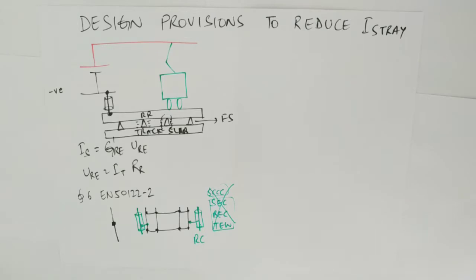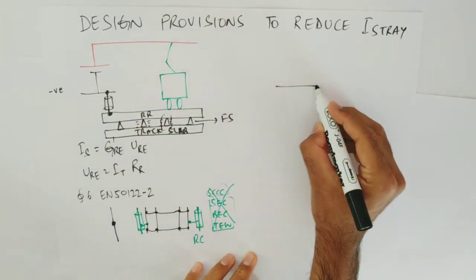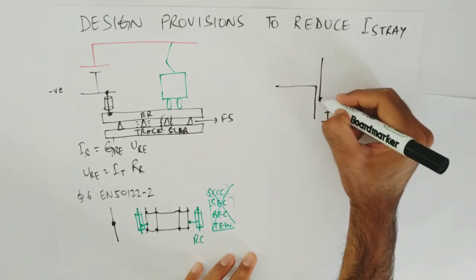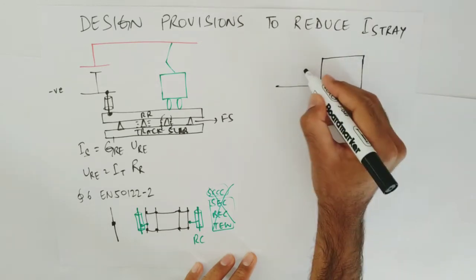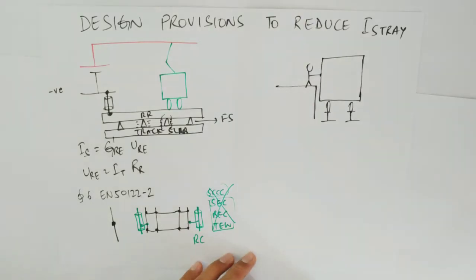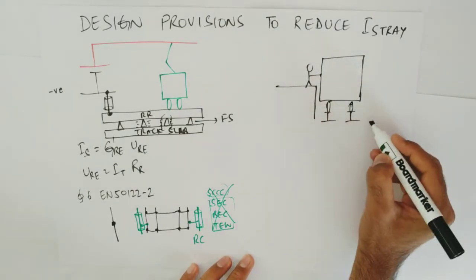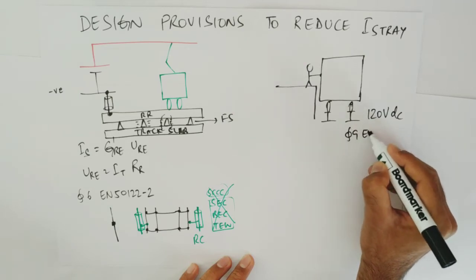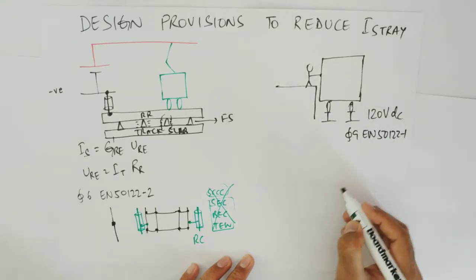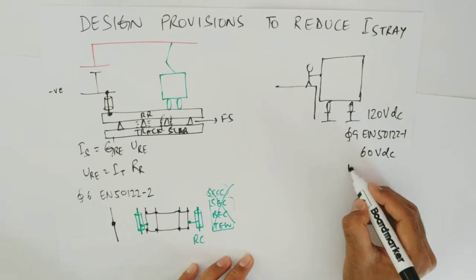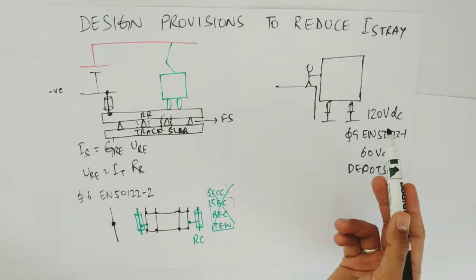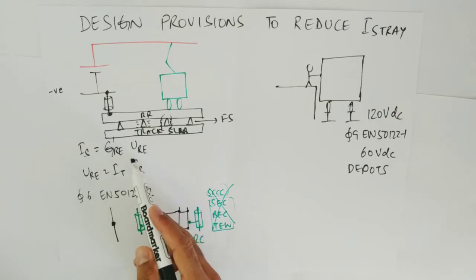However, this has a problem. Suppose we have a station with a platform and running rails, and a person is standing and touching the train. By touching the train he is exposed to the running rail potential. If the running rail potential is above the limit of 120 volts DC — given in clause 9 of EN 50122-1 (60 volts DC for depots) — the person can be electrocuted. The rail potential can increase when current is higher or when resistance increases, such as in an N-1 case.